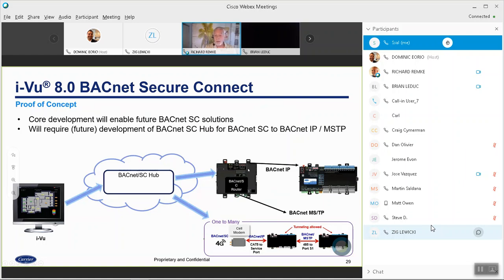One would be putting BACnet Secure Connect into our router, and so that would make a secure connection from i-Vu down to the building on IP, and then you would have the choice of continuing BACnet Secure Connect in the building, or just using normal BACnet over IP, BACnet MSTP.